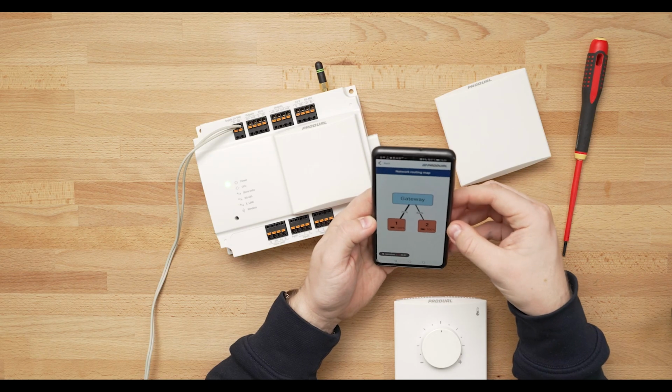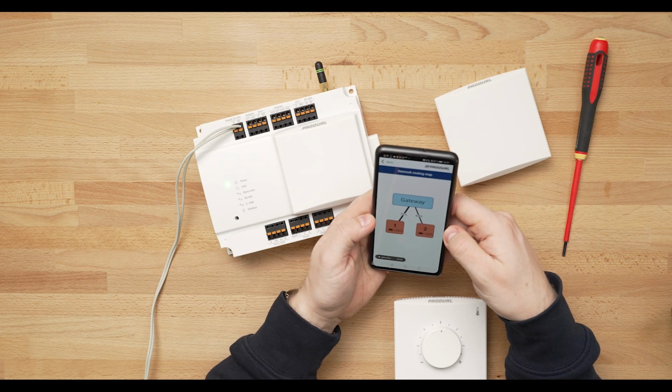If the power consumption doesn't go to the green level, there is usually some kind of topological challenges, or there is some kind of faulty installation settings, like too fast polling interval, or lots of transmitters are routing through one transmitter, which is causing a little bit higher power consumption. Where this will affect is the battery lifetime.